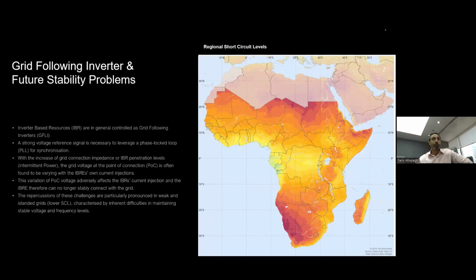When I say independence of operation, the grid forming inverters can operate independently without the need of a strong voltage reference. It creates its own voltage reference and frequency, and could maintain the voltage and frequency, creating a virtual capability, which is hardware and software. This is the future that we believe in. Enhancing stability can respond more effectively to changes in grid conditions, such as sudden loss of generation. So let's say there's a cloud that comes over the solar system, there's a huge drop.